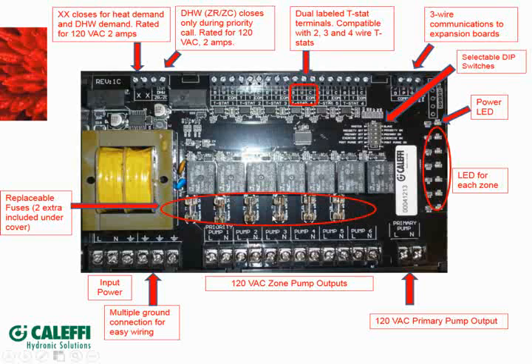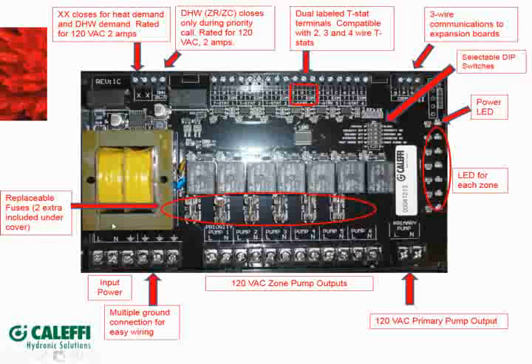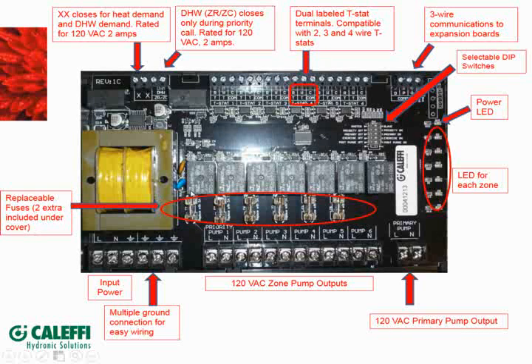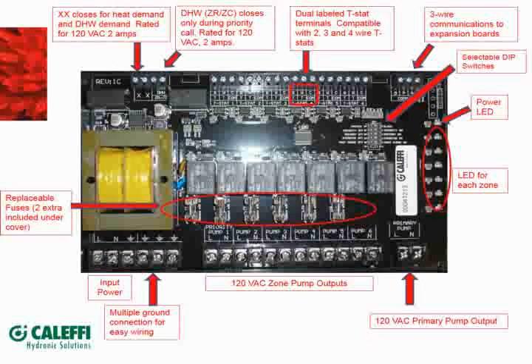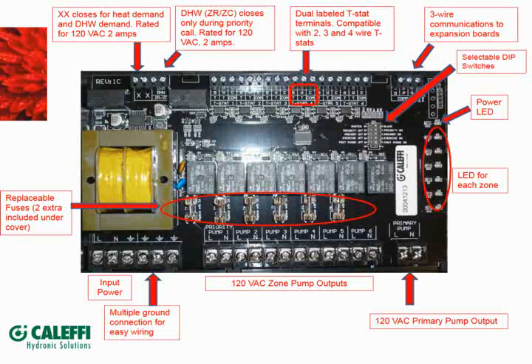And then this is where all of the replaceable fuses are. 5 amp slow blow fuses, and we got a couple of spares under the hood too if you do pop them. And then you can see where the transformer fuse is up there, or breaker, or whatever you call it. I guess it's a resettable fuse. Yeah, these are the resettable fuses. We actually do that on both the 120 volt side and the 24 volt side. So if you get a short, you're protected in a lot of different ways, so that you don't cook the whole board if you short out a thermostat or something. Yep.